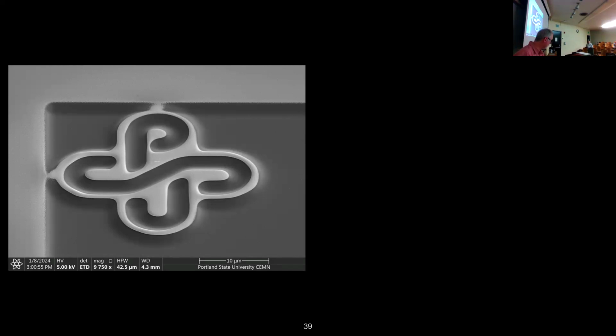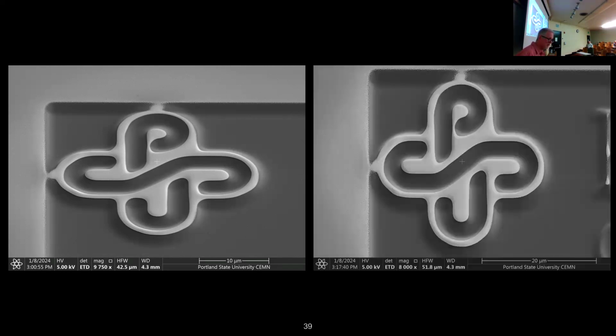Anyone have thoughts on what's wrong with this? Does it look funny? Squash. Yeah, it's a little squashed because it's a 52-degree angle, and I didn't have the scan compensation set correctly for this particular imaging mode. I reset it, and then it came out a little bit more square, more like it should be. That's more how it should be.